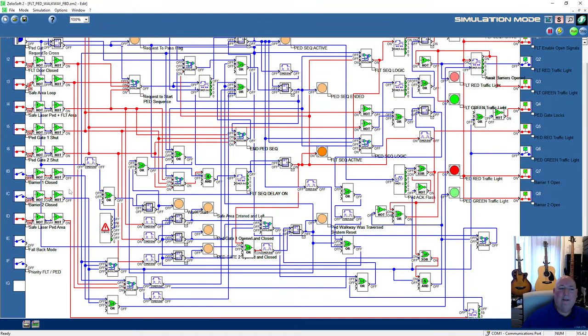So it's basically waiting for the barriers to become open or not shut. Normally those output commands would activate the barriers. We don't have any barriers, so we have to do it manually. Right, what else? So we're in forklift truck mode. We activate the door, safe area and safe laser, that's all good. Okay, we put a request in. I get a request coming up, it switches the gates, barriers off, locks the gate, unlocks the gate, switched on to PED mode, we're not counting down. So we've just walked into one laser, then we've just broken another laser at the same time.